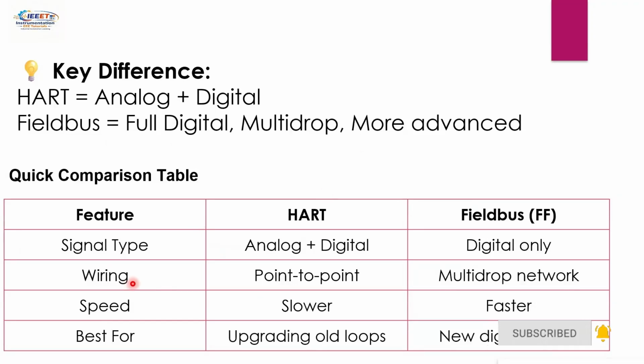Looking at some features, we can distinguish HART and Fieldbus Foundation further. Signal type: analog and digital in HART, digital only in Fieldbus. Wiring: point to point in HART, multi-drop network in Fieldbus — this is the beauty of Foundation Fieldbus. Speed: HART is slower, Fieldbus is faster. Best use: for upgrading an old loop, HART can be considered, but if we want to go for a new digital plant, we should go for Foundation Fieldbus.